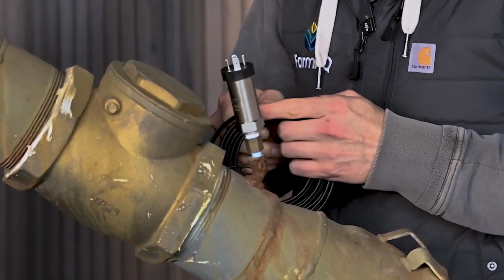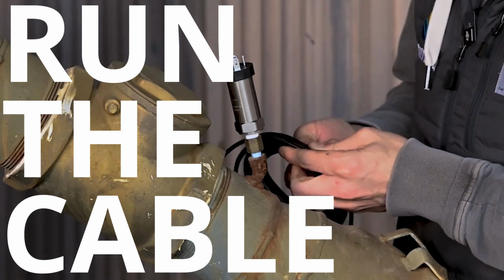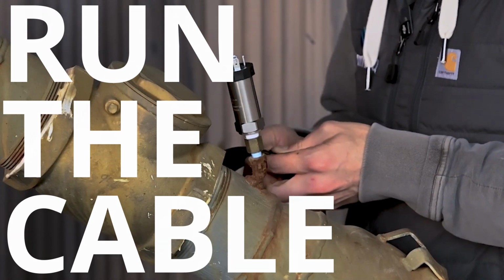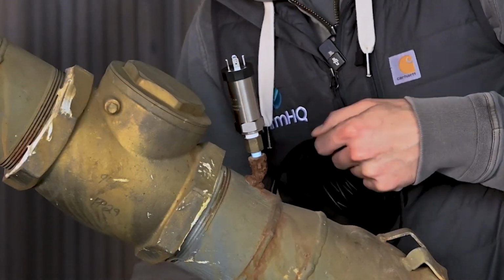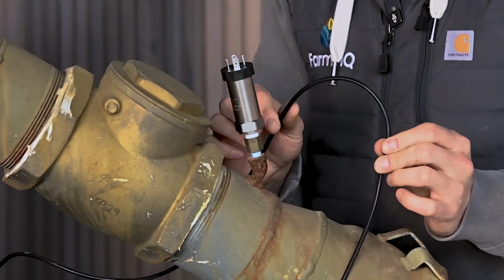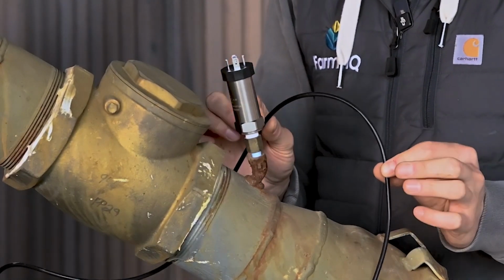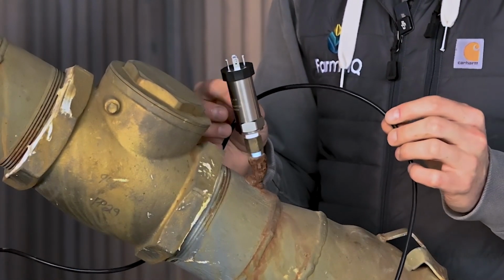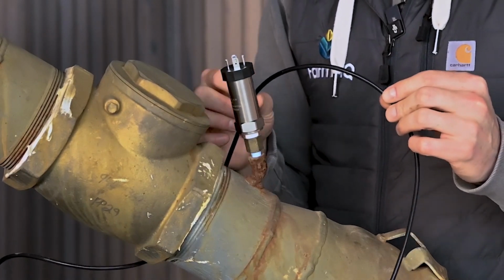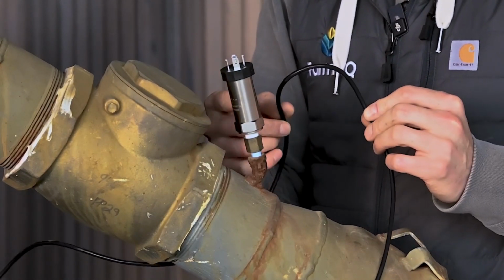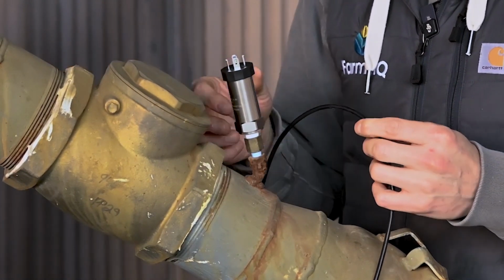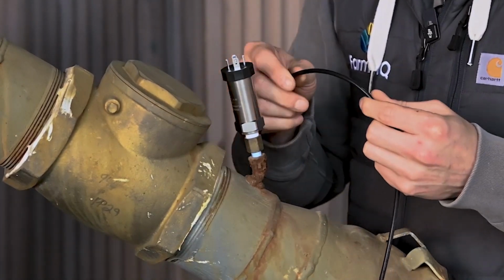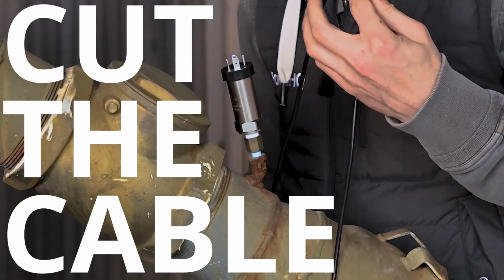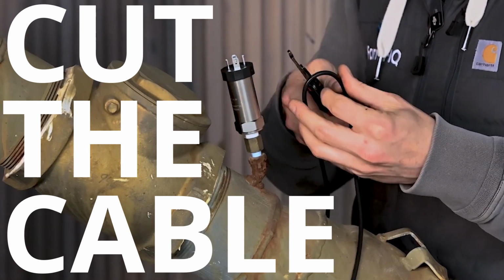Next up, we need to run our cable. I could reuse the existing cable, but I feel like it's probably best practice to start fresh. All right, we've run our cable here. Every replacement transducer will come with an updated cable. It's important that the colors match, and so we recommend that you use the cable that's included with the replacement, even if you already have an existing cable on your machine. So what I'm going to do is go ahead and cut this cable to fit. I'll leave a little bit of slack in the connection just so we can zip tie it appropriately, but I'm going to go ahead and cut the cable.